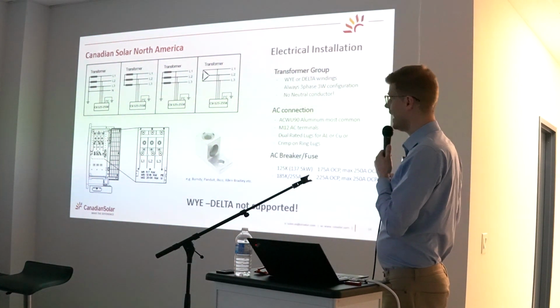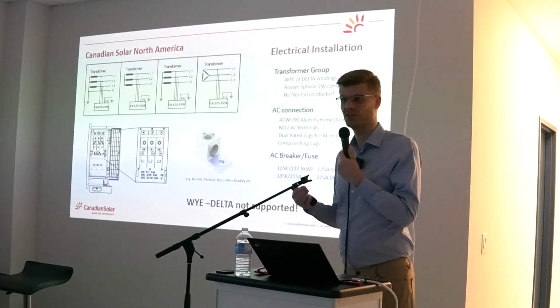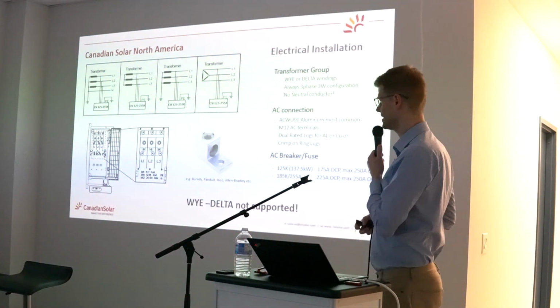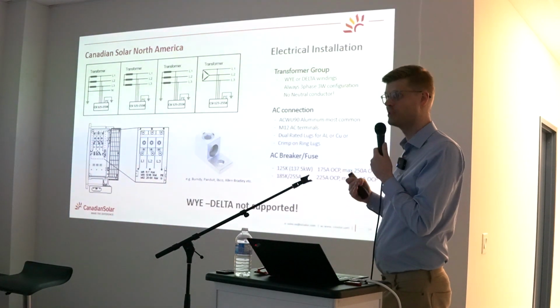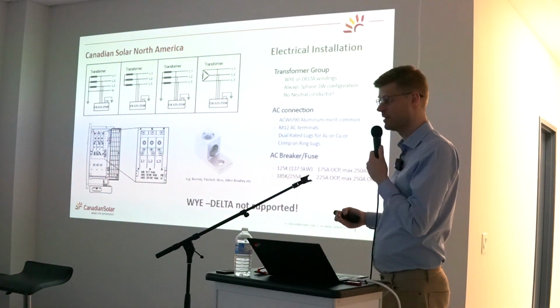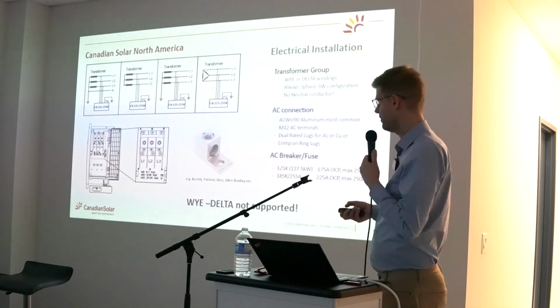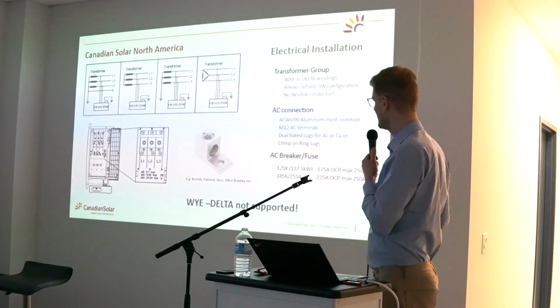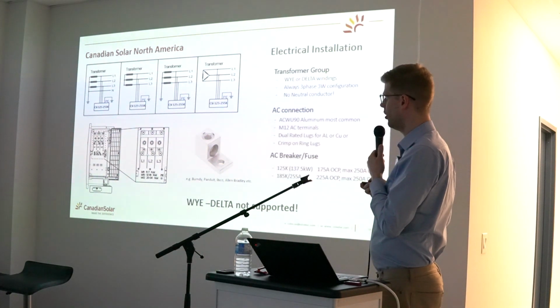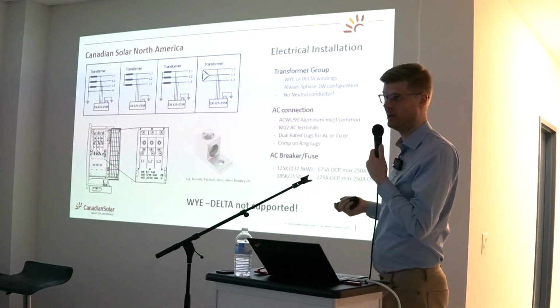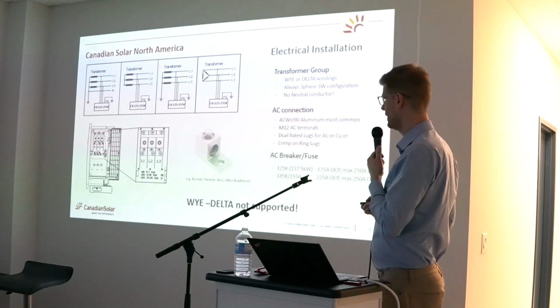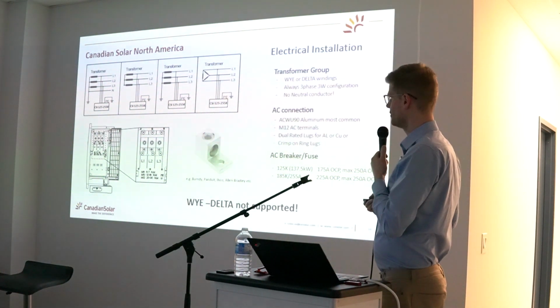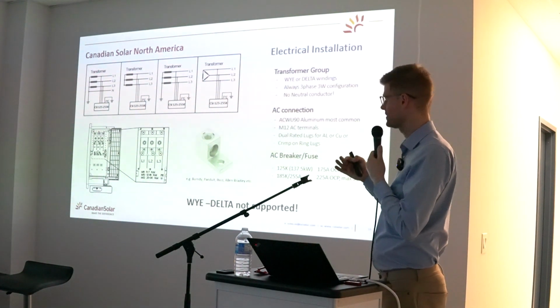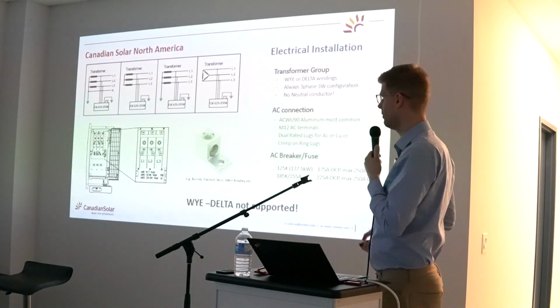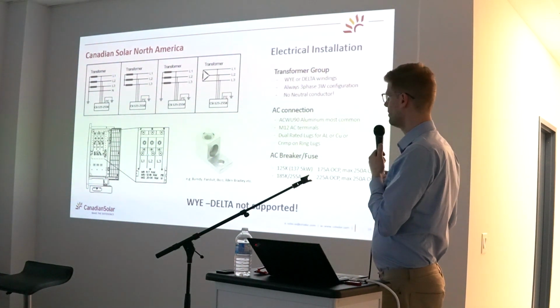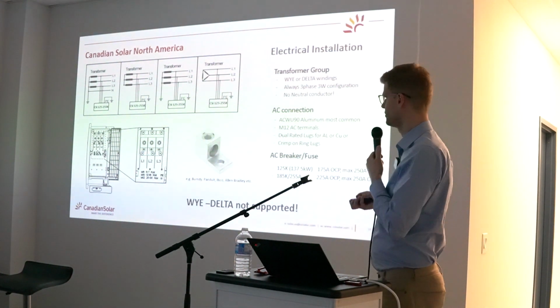The unit at that power level needs relatively large AC conductors, and since copper went up in price significantly, for these kinds of installations most installers are using aluminum conductors. Much easier on your financials and the budgets you're allocating. And you can use aluminum on those studs with a typical mechanical lug. That's the most common installation method. They're available from multiple companies. And you transition from the typical copper terminals into a dual-rated aluminum and copper terminal.